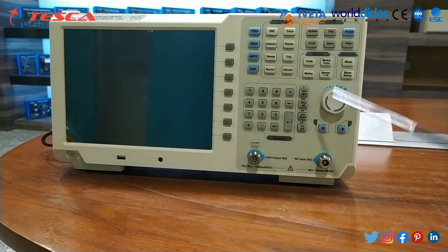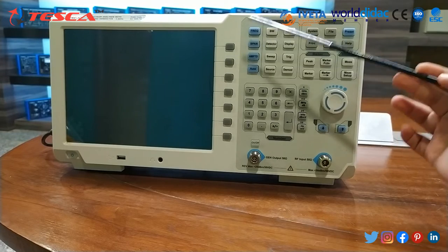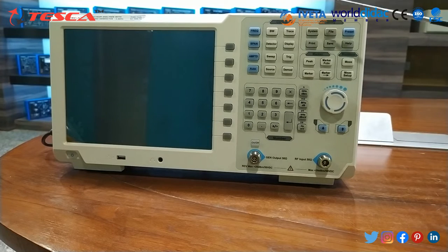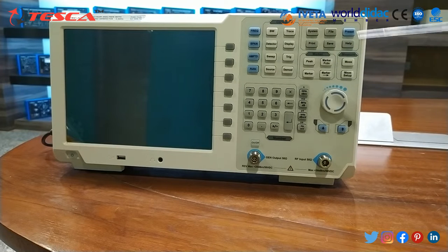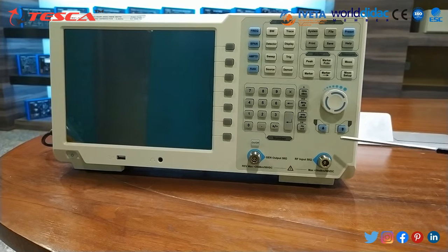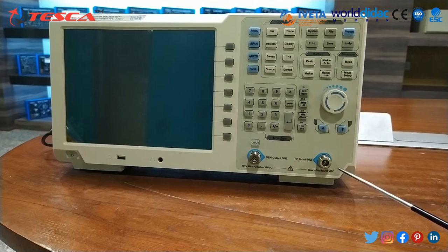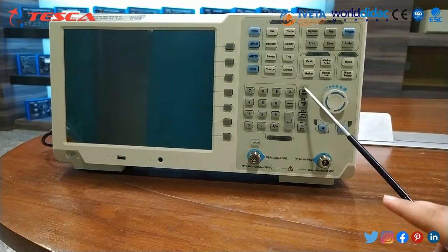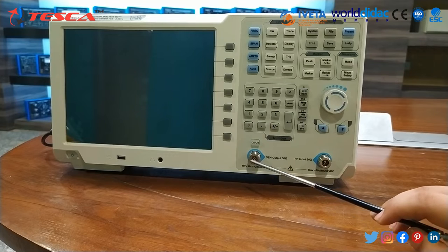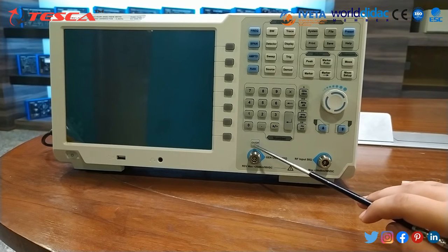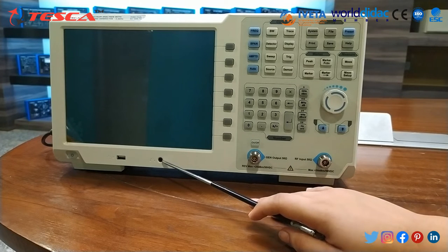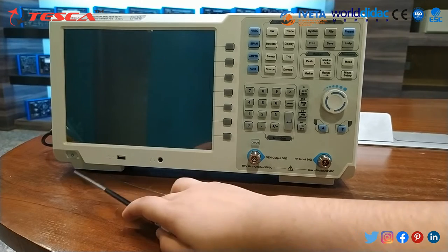This is the spectrum analyzer and we will have a detailed discussion of this panel. These are the manual soft keys, this is the LCD display, these are the function keys, and this is the knob. These are the arrow keys to move upward and downward, and this is the RF input connector. These are the unit keys, the numeric keys, the tracking generator output connector, the tracking generator on/off button, the earphone interface, the USB host port, and the power key.